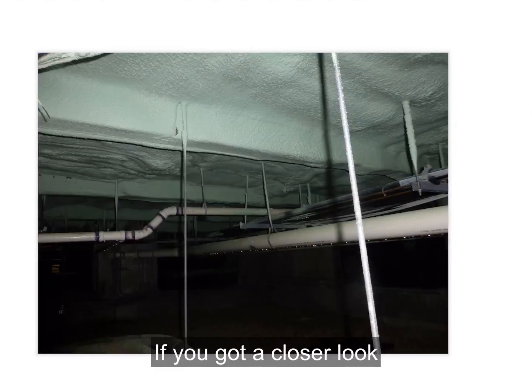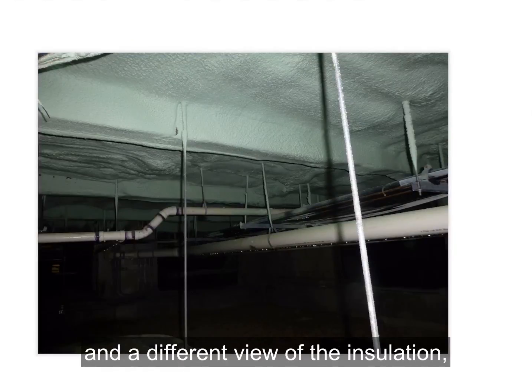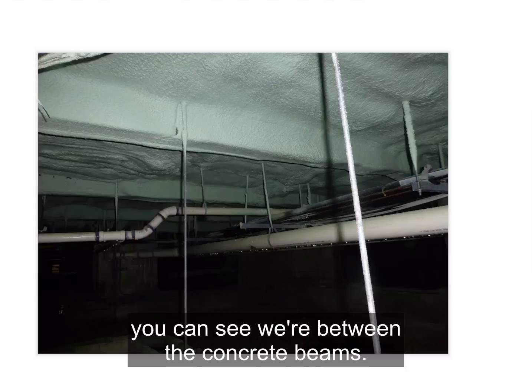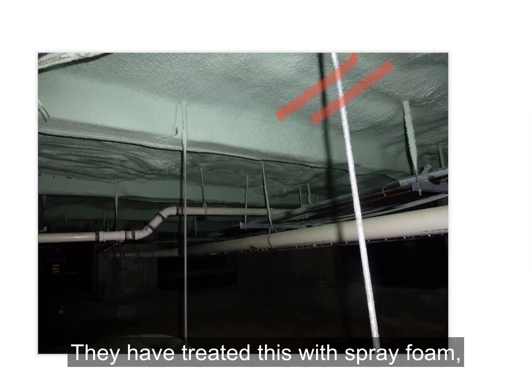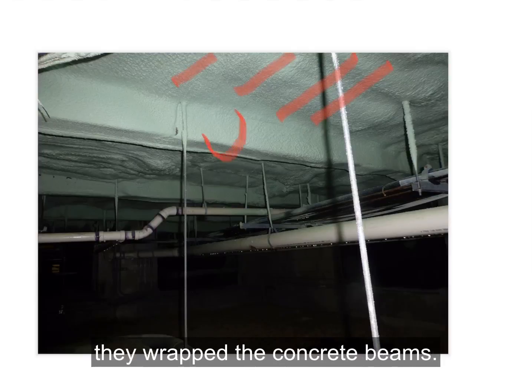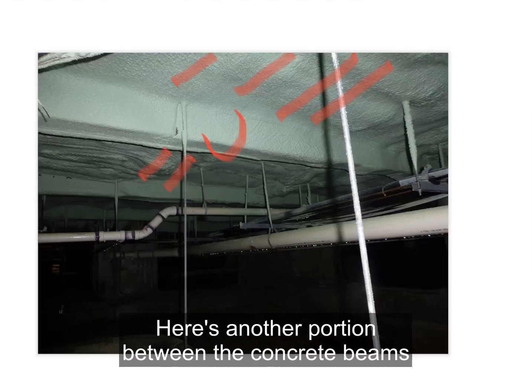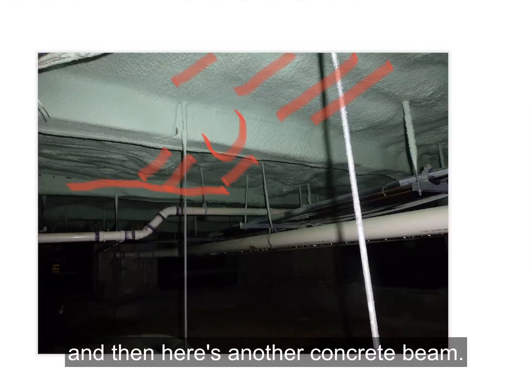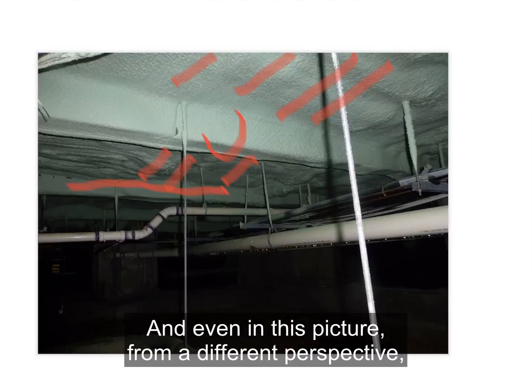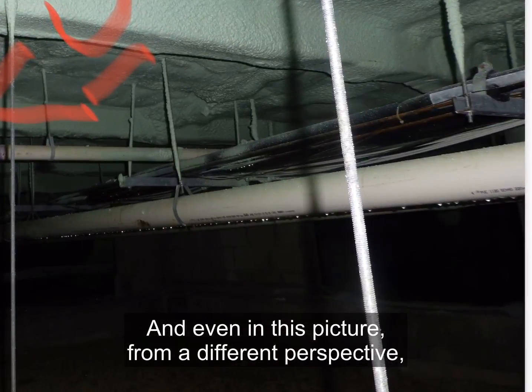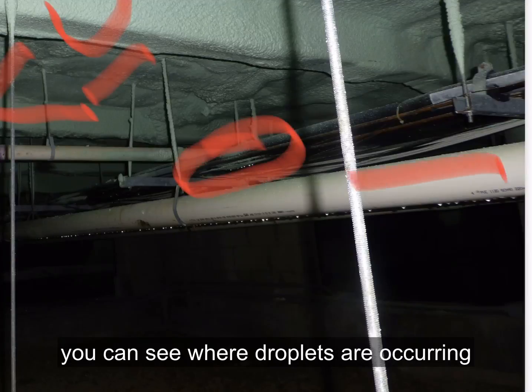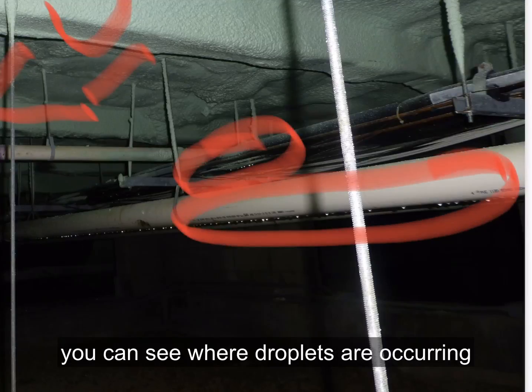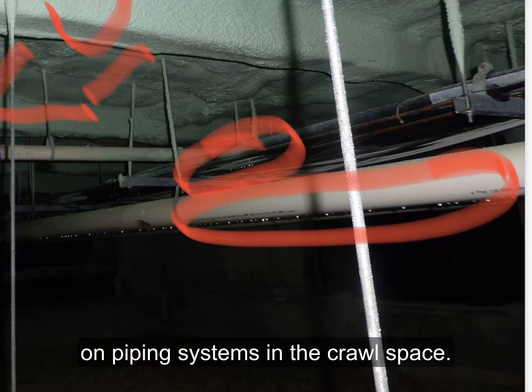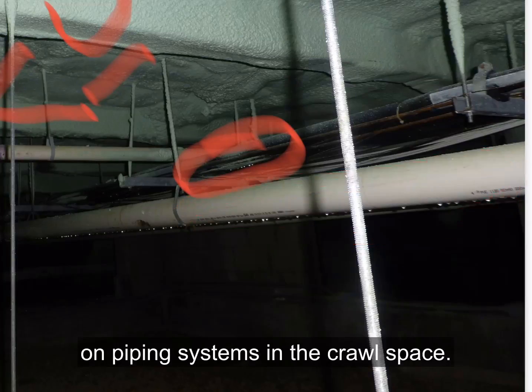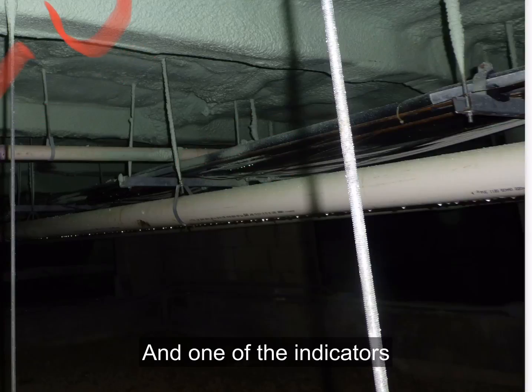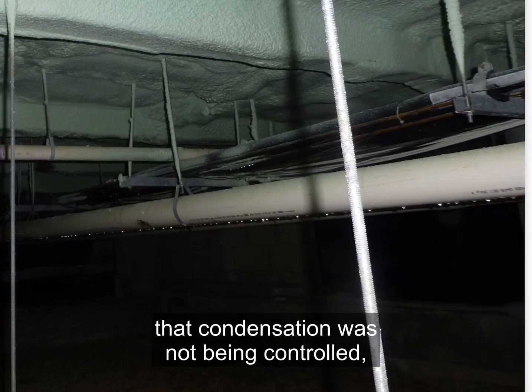If you get a closer look and a different view of the insulation, you can see where between the concrete beams, they have treated this with spray foam. They wrapped the concrete beams. Here's another portion between the concrete beams, and then here's another concrete beam. And even in this picture, from a different perspective, you can see where droplets are occurring on piping systems in the crawl space, one of the indicators that condensation was not being controlled.